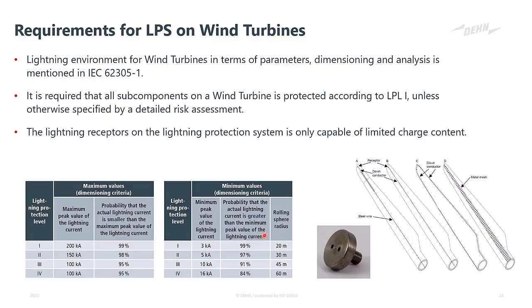Now, it is a requirement from 61400 that lightning protection systems in wind turbines comply to lightning protection level 1. So they have to have the best lightning protection level, unless otherwise specified by a detailed risk assessment. Now, that's typically not something that you would see. Manufacturers would just manufacture it according to level 1. But if you don't know, please inquire this with the manufacturer on your wind farm as part of your wind farm design.